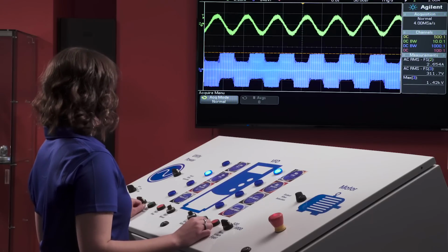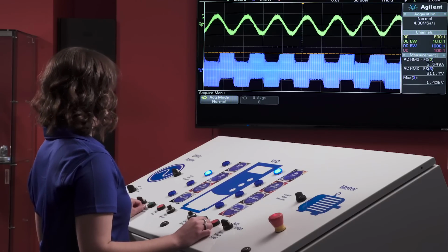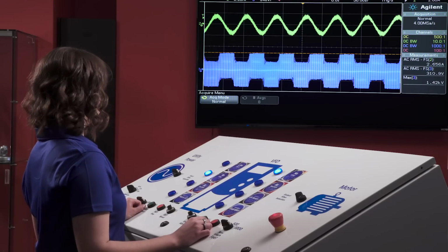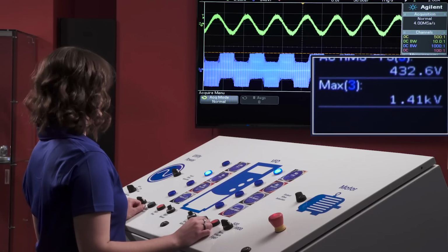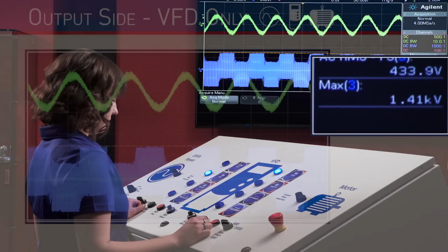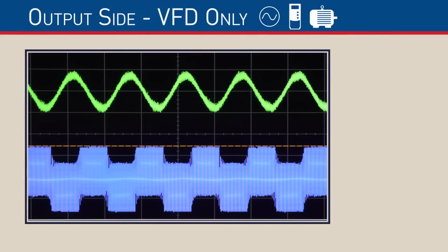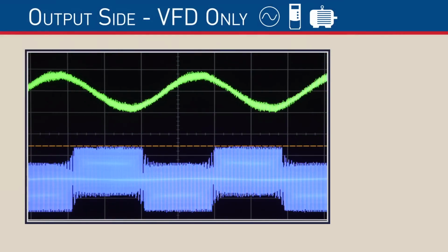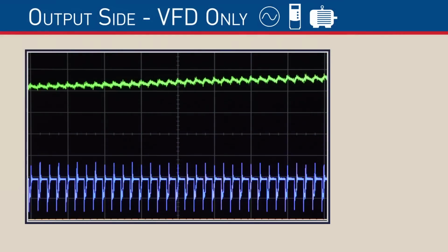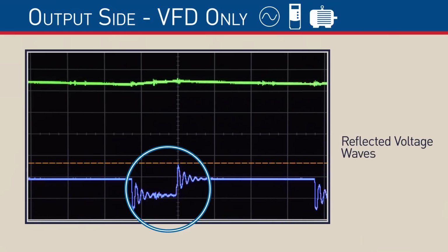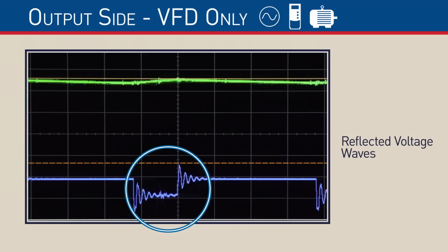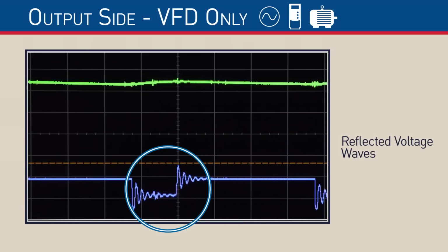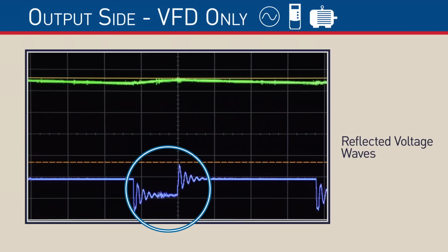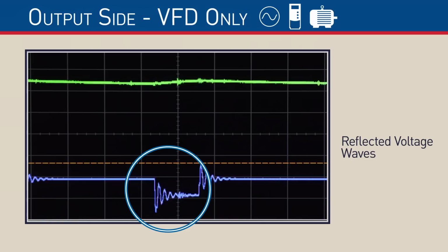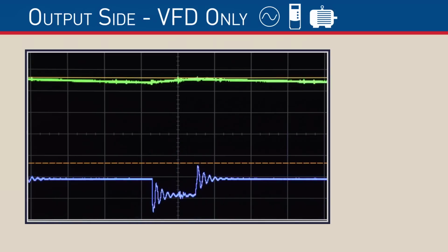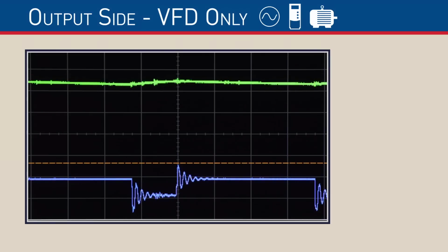As we bring the VFD online, we notice right away that the voltage waveform is severely distorted. In fact, we're pushing about 1400 volts out to the motor and getting dangerously close to the peak insulation voltage rating of the motor. As we zoom in, we can also see that we are experiencing reflected voltage waves, or ringing, that when combined with the output voltage may result in pulsing over the voltage rating of the motor several times within one PWM cycle. These factors can greatly reduce the life of the motor.